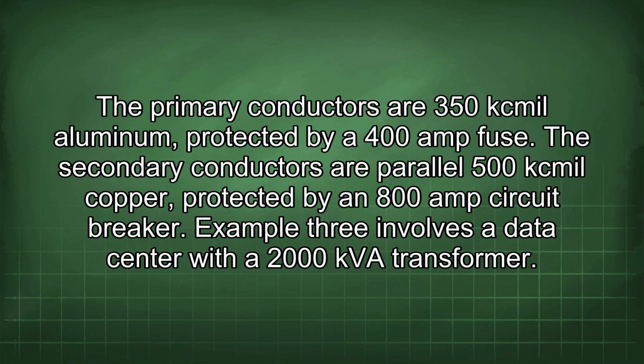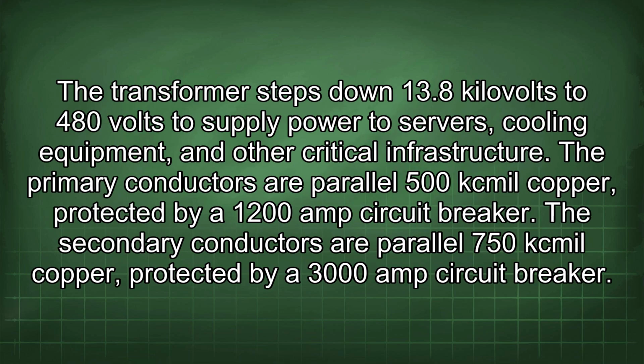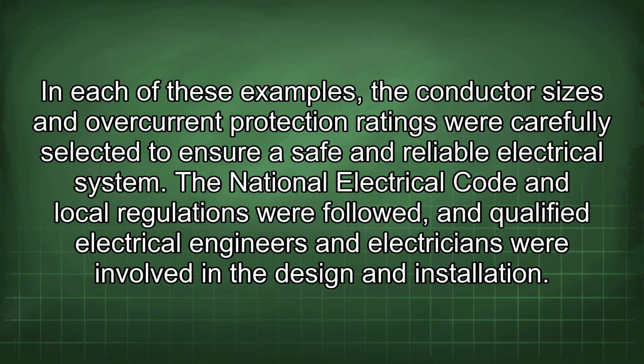Example 3 involves a data center with a 2000 kVA transformer. The transformer steps down 13.8 kV to 480 volts to supply power to servers, cooling equipment, and other critical infrastructure. The primary conductors are parallel 500 kcmil copper, protected by a 1200 amp circuit breaker. The secondary conductors are parallel 750 kcmil copper, protected by a 3000 amp circuit breaker. In each of these examples, the conductor sizes and overcurrent protection ratings were carefully selected to ensure a safe and reliable electrical system. The National Electrical Code and local regulations were followed, and qualified electrical engineers and electricians were involved in the design and installation.